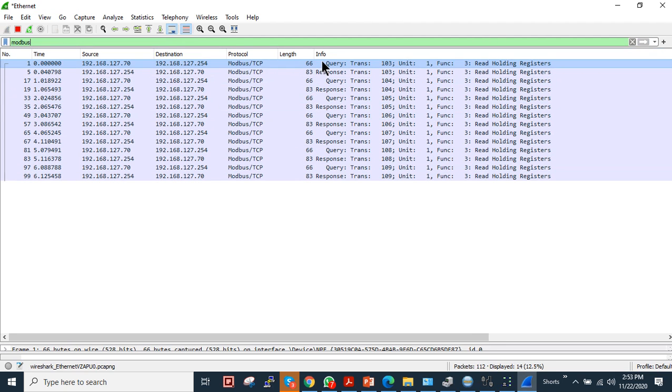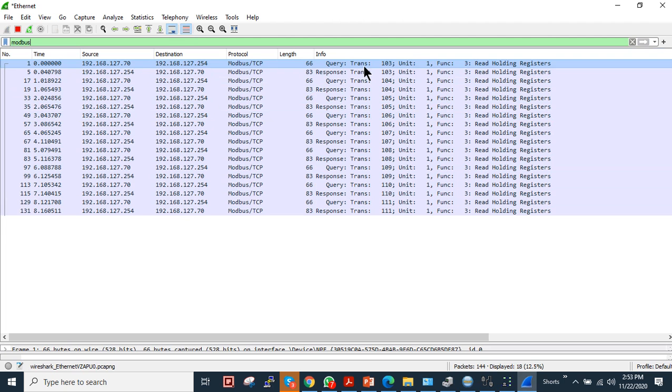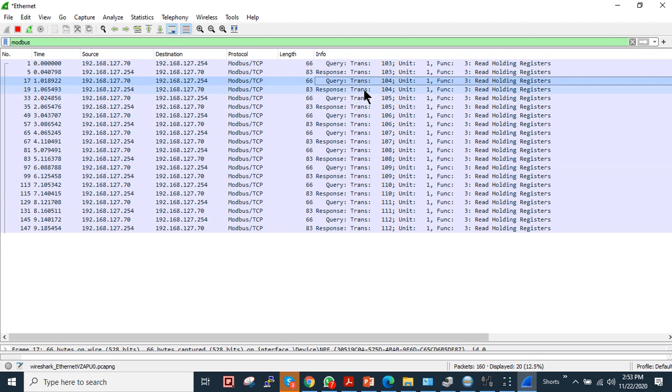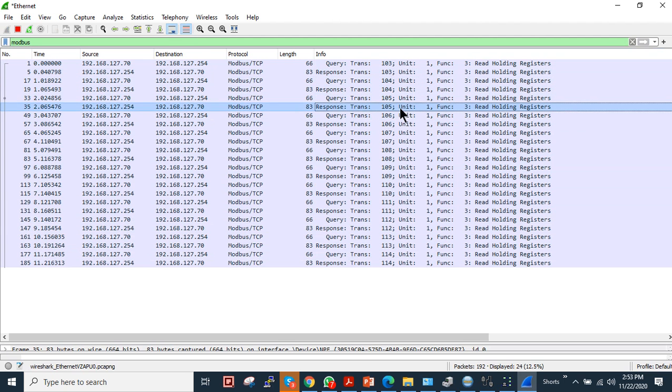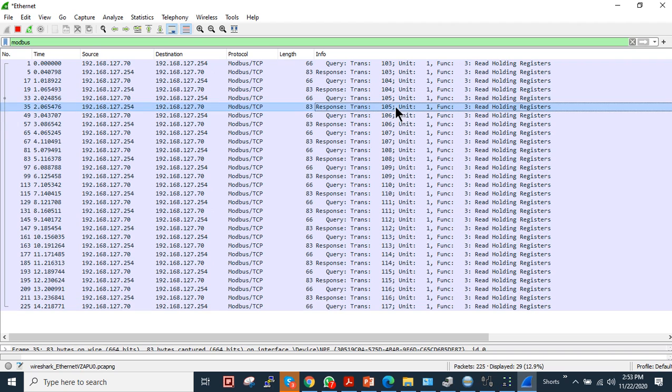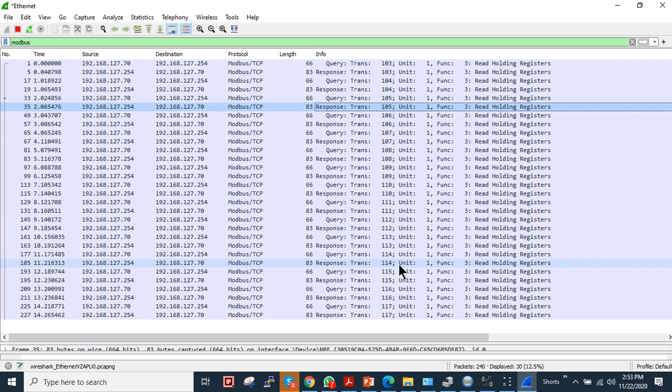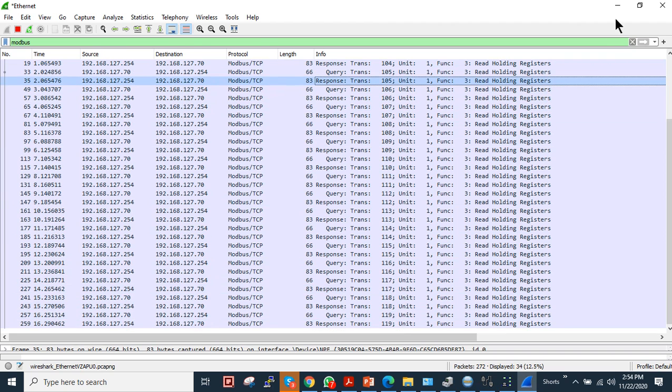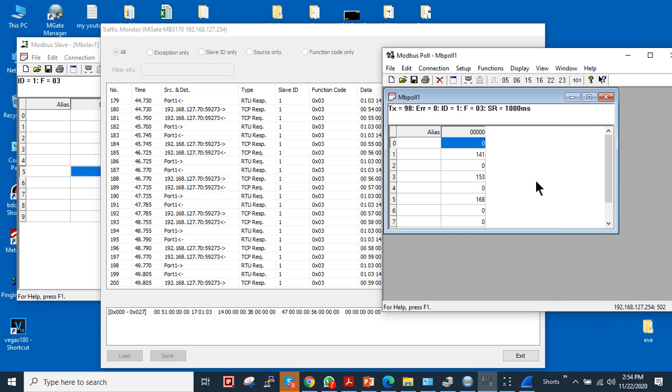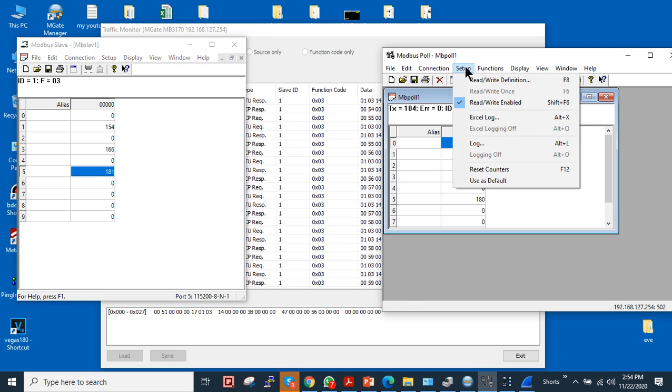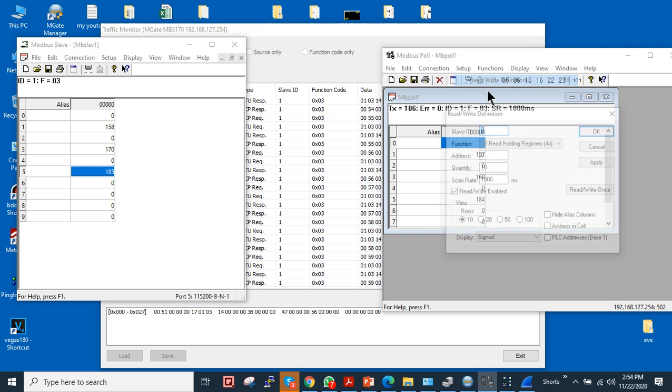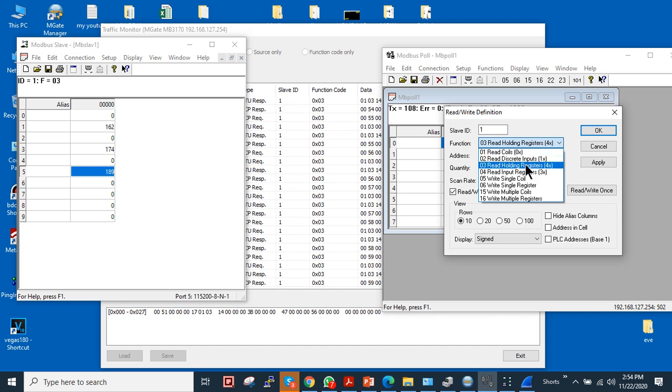Choose Modbus and click. As you can see, I am having query and response - query, response, query, response for everything. You can see the values. Values are working fine. If you want to change the read definitions, you can change the definitions here during your testing.